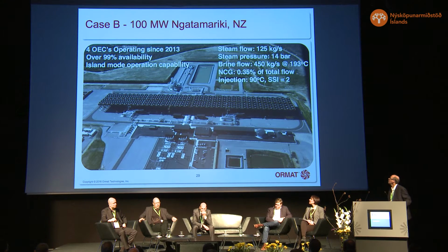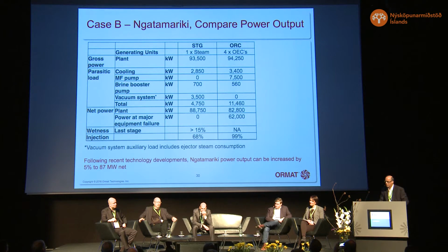This is the general overview of the power plant. What we can see here is that even though probably an STG would provide 6 megawatt more than an ORC system, the client requested a binary system, which is air-cooled and makes full reinjection of the fluid. As for the 6 megawatt, if we would do this power plant today, since the installation we developed some improvements that would boost the power output to 87 megawatt and probably decrease the difference to only 2 megawatt.